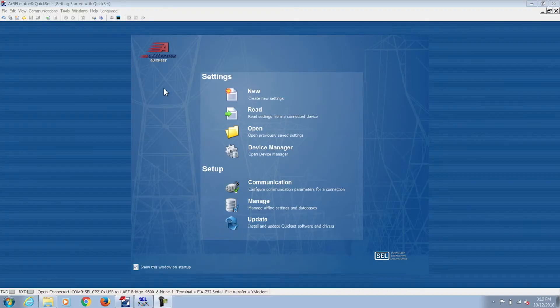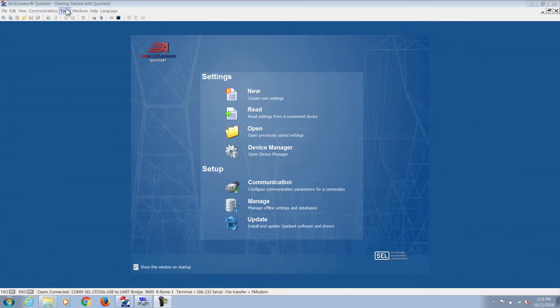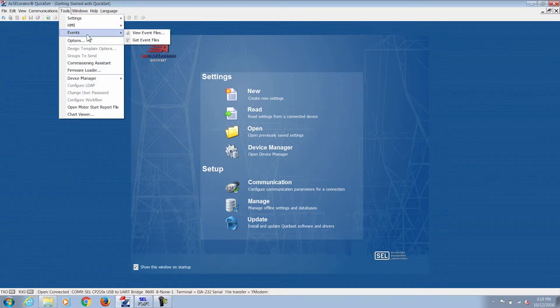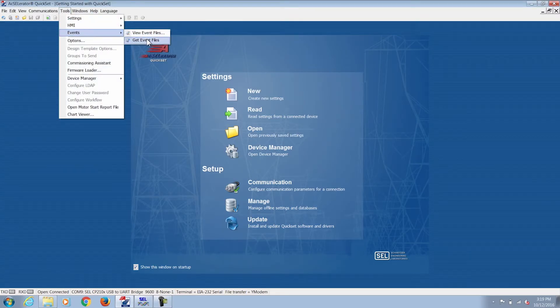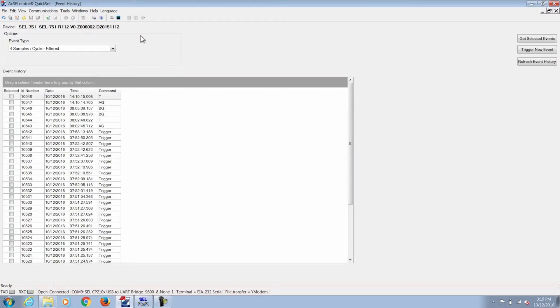You gather the event through AcSELerator QuickSet by going to Tools, Events, Get Event Files. The event history overview is going to show up and give you an outline of all the events that have occurred and were recorded on the relay.